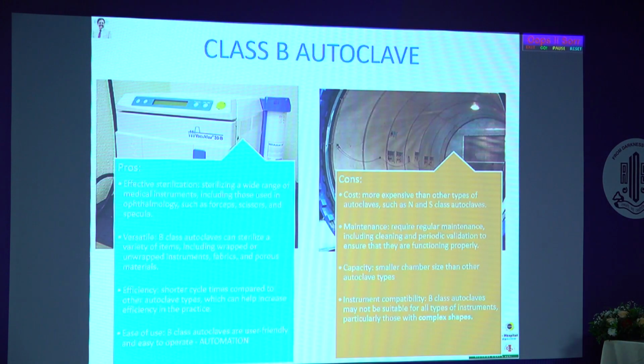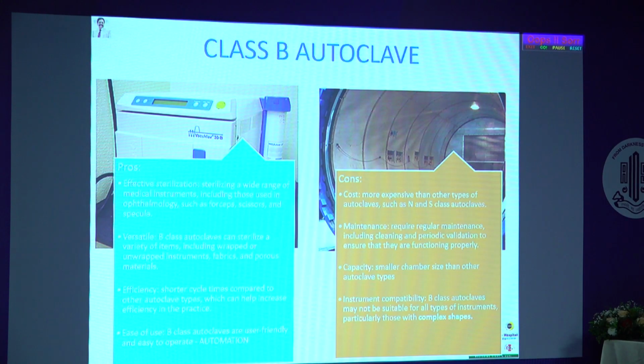And so these are the pros and cons. The Class B autoclave has very effective sterilization, almost close to 100%. Particularly when we are using it for small instruments, to protect the sharpness we can use a wrapped cycle. It's quite versatile for every fabric and porous material. Efficiency: very short cycle time. Once the chamber is heated, the second cycle or the second load becomes easier, within 10 to 15 minutes. And a lot of cycles are there. There are 12 cycles in the Class B autoclave. I think Dr. Rajiv or Kumaran will be covering that.